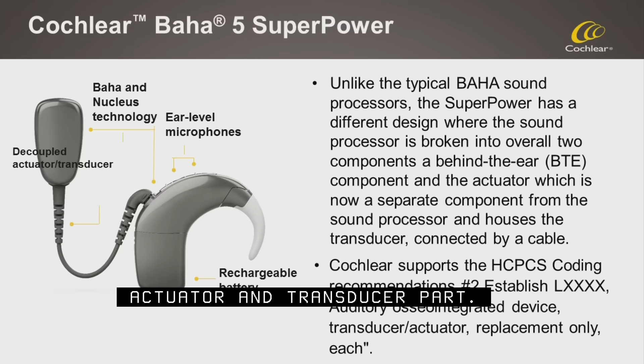So in conclusion, unlike any of the typical Baha sound processors that are out there, the Superpower has a very different design from our standard AOIs. And what we have done, as I mentioned, is that we've broken out the traditional single component unit into two different components, where now there is a behind the ear component as well as a decoupled actuator and transducer part. And Cochlear does support recommendation number 2, the establishment of a new code for the transducer actuator as the replacement component going forward.